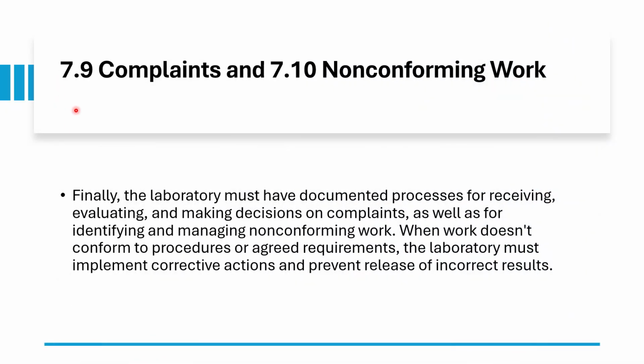Now coming to clauses 7.9 and 7.10, these two clauses go hand in hand. The laboratory must have a documented process for receiving, evaluating and making decisions on complaints as well as for identifying and managing non-conforming work. When work doesn't conform to procedures or agreed requirements, the laboratory must implement corrective action and prevent the release of incorrect results.